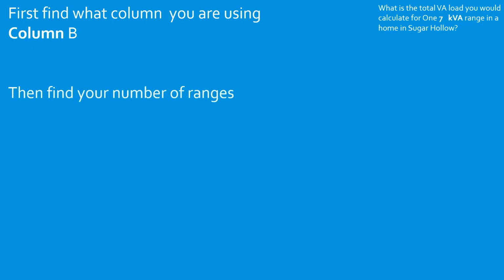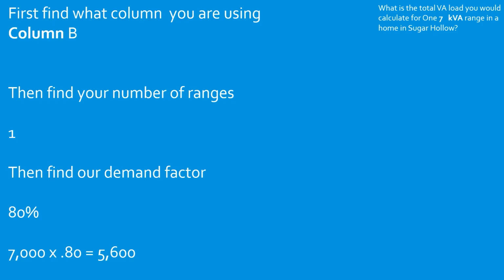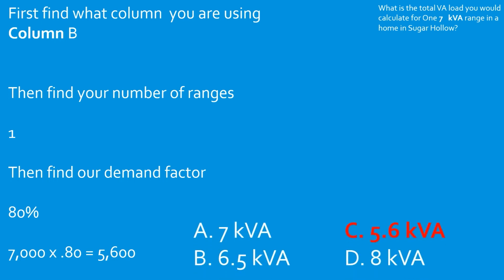Now we're going to come over to the left-hand side for our number of ranges. We have one range. We come over and tee off with column B to find our demand factor. Ours is 80%. So now we come back and we take our 7,000 VAs from our one range. We're going to multiply that by 0.80. That's going to give us a new total of 5,600 VAs, and we're going to select C.